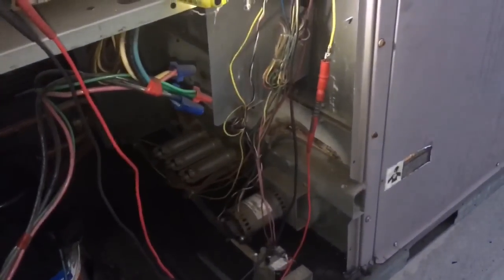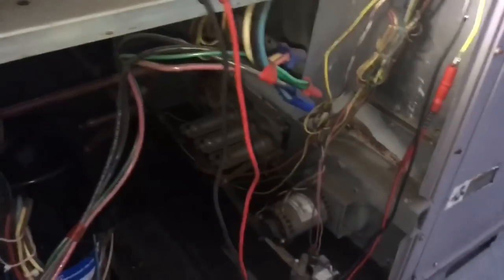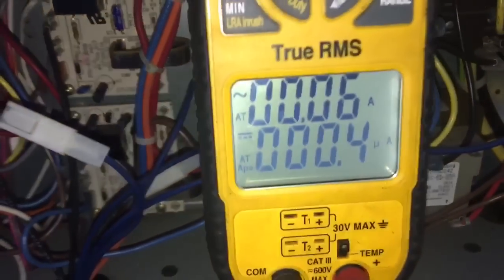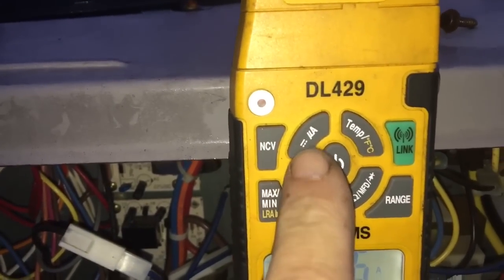Go ahead and crank it back on. Sometimes, you know, just the flame sensor is dirty, but before cleaning it I thought we'd give it a try just to see what it looks like. We're gonna be checking the microamps DC, which is off this button on the DL 429.